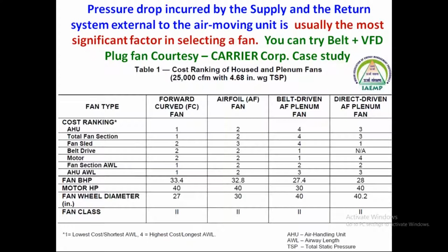And it's direct driven, which means it is 28. And the motor HP needed for this application: normally all the fans want 40 HP except the belt driven plenum fan, which needs only 30 HP. So straight away you can save on the inventory, on the motor capacity, and on the switchgear capacities. The rated capacity may be 40 HP, but the running BHP is only around 27. This much energy saving is possible in this aspect.